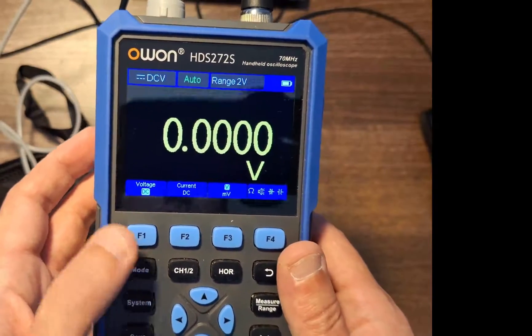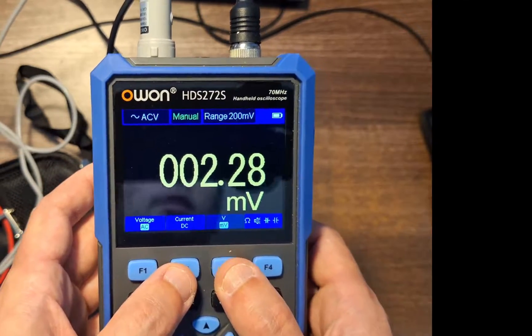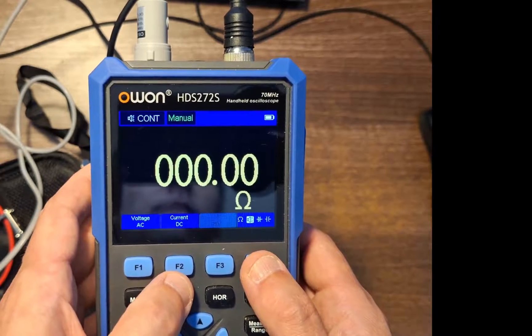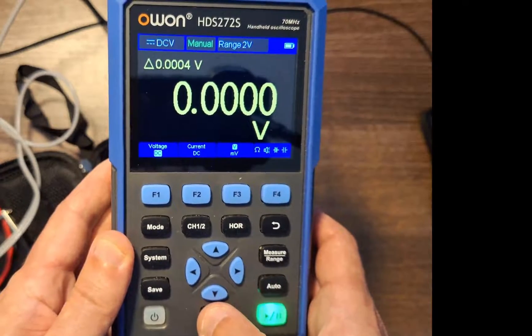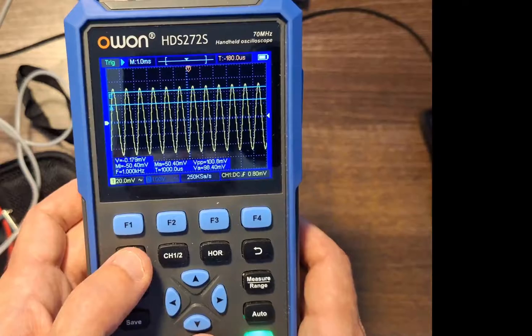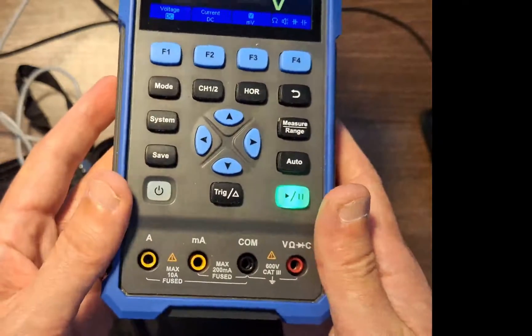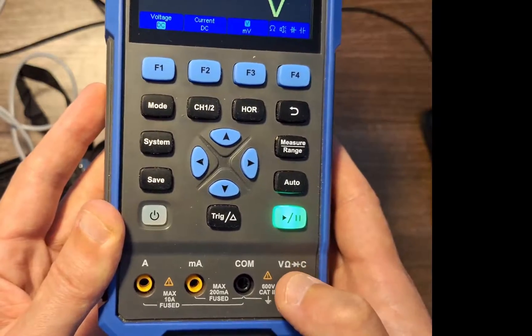Let's move on to the voltmeter. I'm not measuring anything at the moment but you get the idea — you can change from voltage AC to DC, change to measure current, and change from millivolts to volts. That button also changes the amps when you're measuring current. You've got your sockets down here for measuring voltage, current, and also capacitance and resistance.